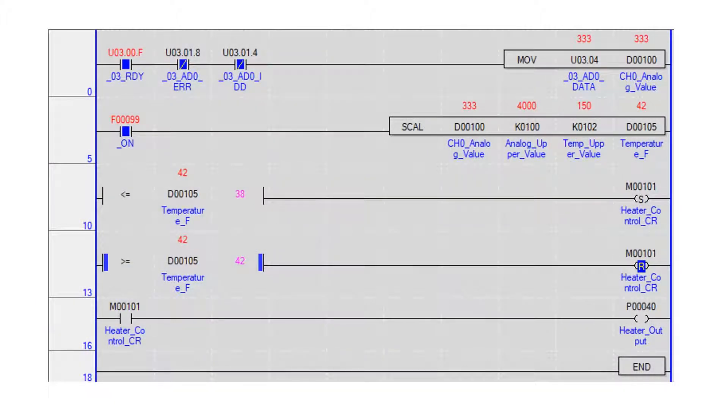To read the analog value, the module ready bit must be on. The channel 0 error bit and channel 0 disconnected bit must be off. A move instruction moves the analog data from the module channel 0 to memory location D100.